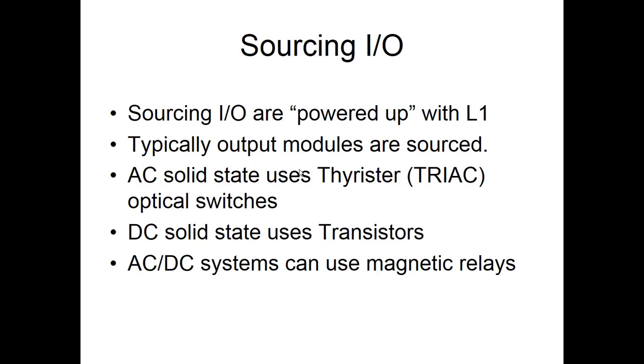A sourcing I/O. So sourcing is you power up the module. So when you have a sourcing output, for example, the first thing you do is you run voltage to it, either L1 or DC plus. Typically, output modules are source. Now, when you get into robotics and stuff, some of these foreign companies do their sourcing and sinking backwards compared to what we normally see. But typically, output modules are going to be sourced, and ours are.